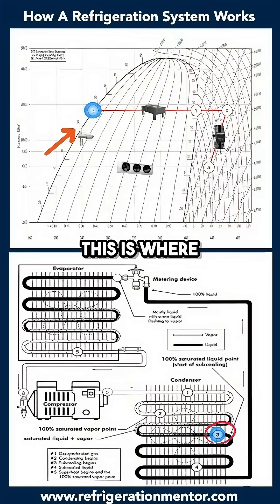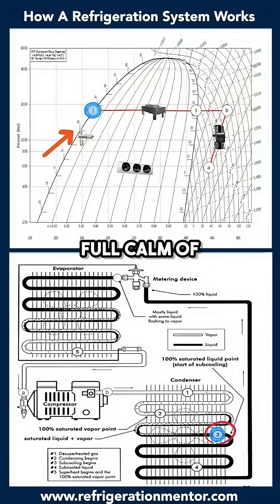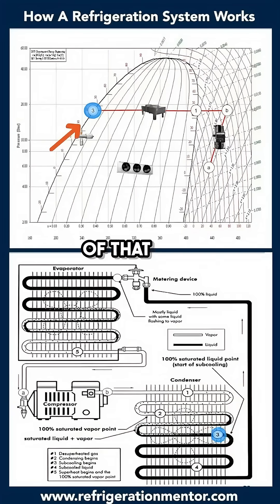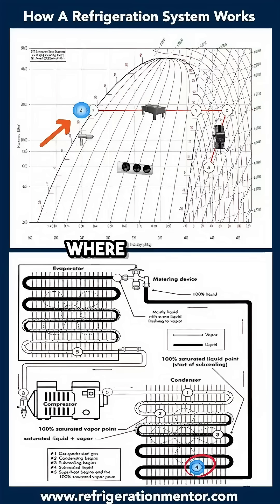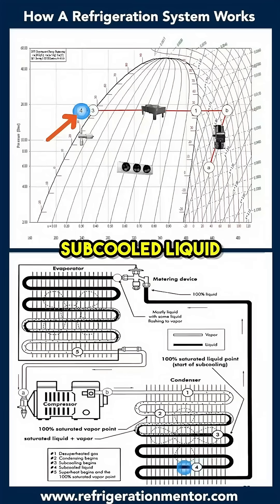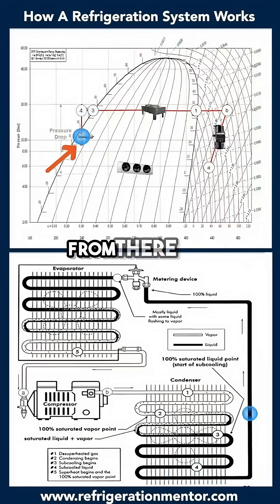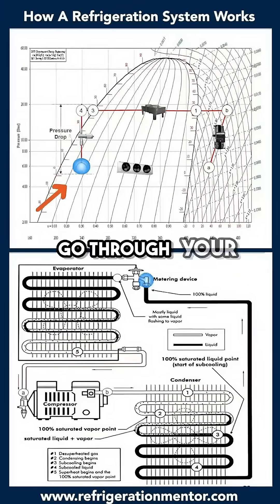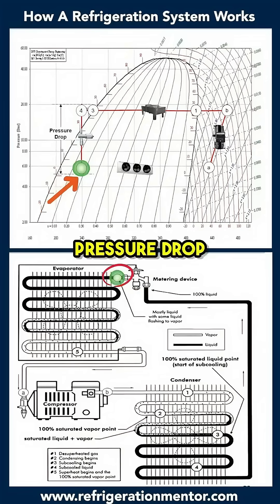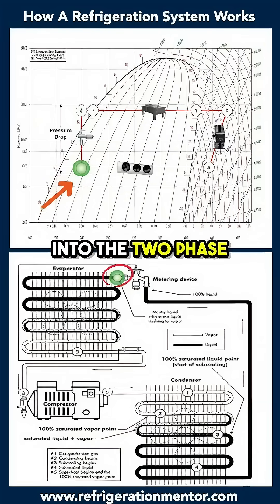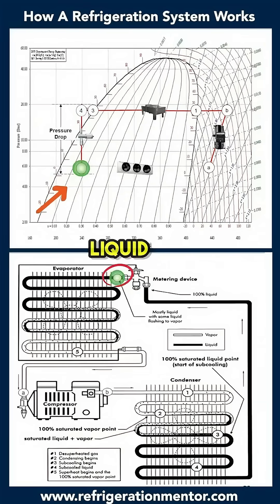By the time you hit that bubble point, this is where your subcooling begins. When you have a full column of liquid, anything on top of that is your subcooling — so this is where you have subcooled liquid. From there you go through your metering device; that pressure drop pulls you back into the two-phase region, where you have both liquid and vapor.